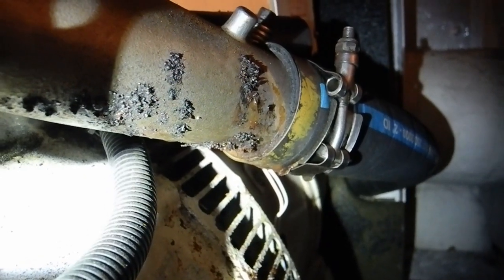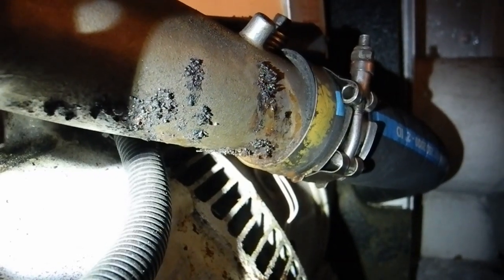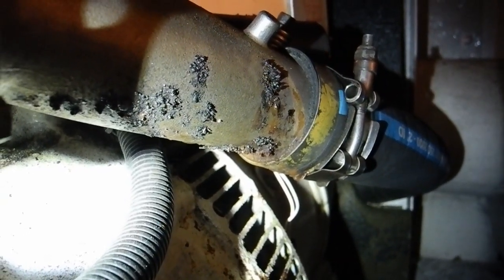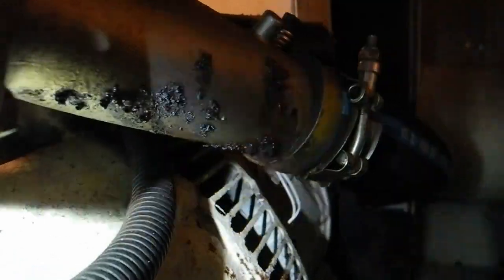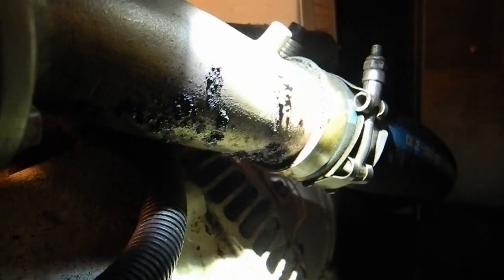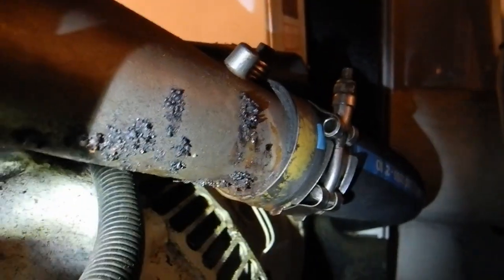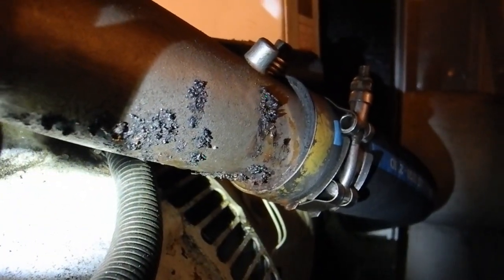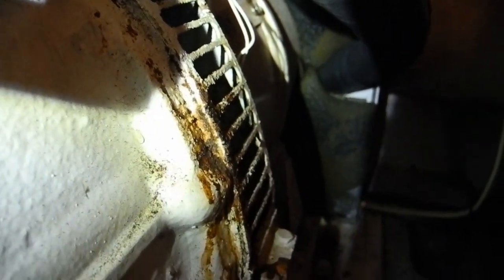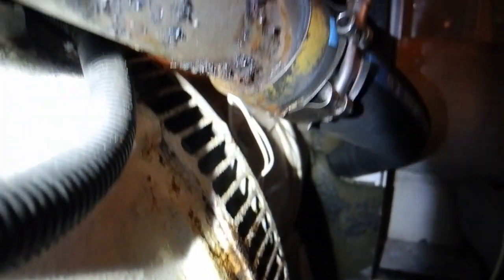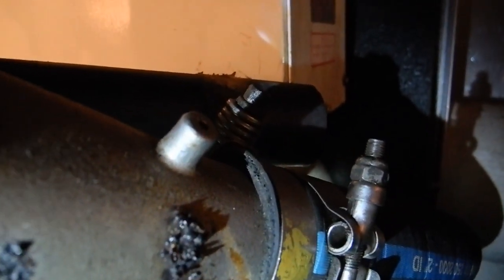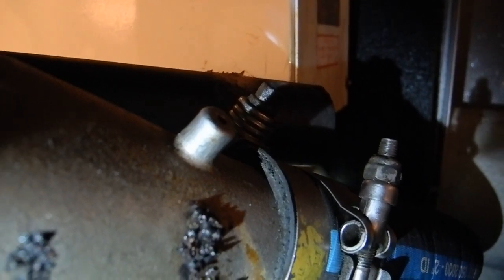I'm looking at this exhaust elbow on a generator. You can see it's got a lot of rust on it and it's silver. That is stainless steel, but look at all that crevice corrosion. This should be replaced immediately. You can see it's leaking water down into the electrical armature. Another thing that's dangerous about this is that little knob right there is missing the thermal sensor.